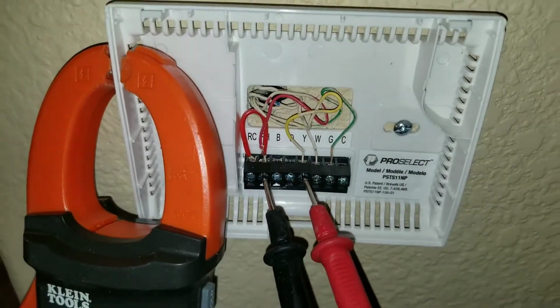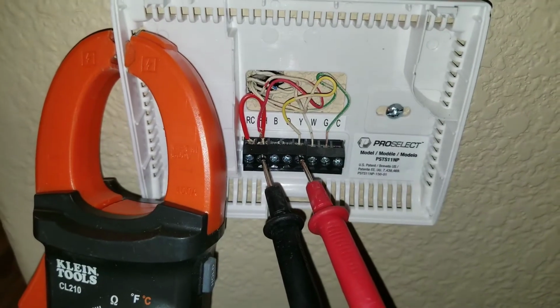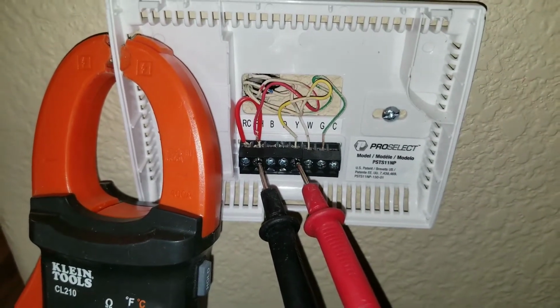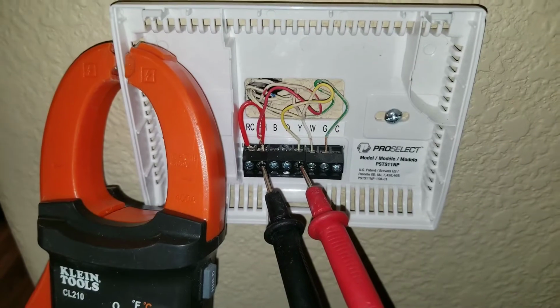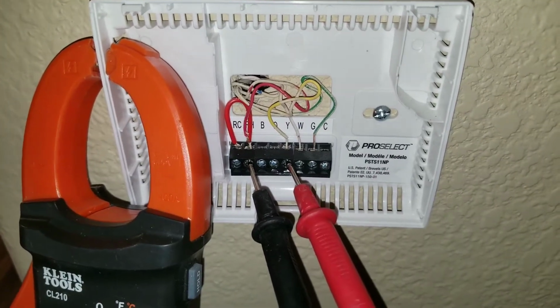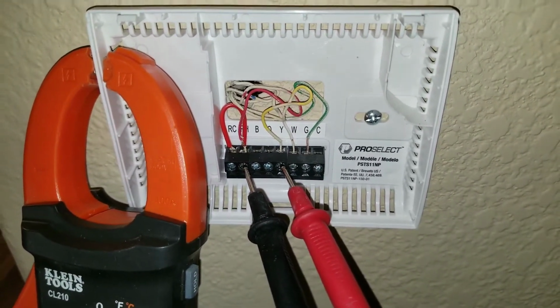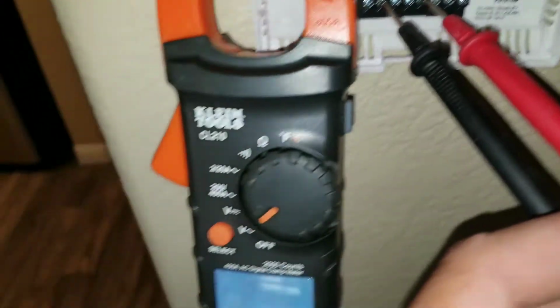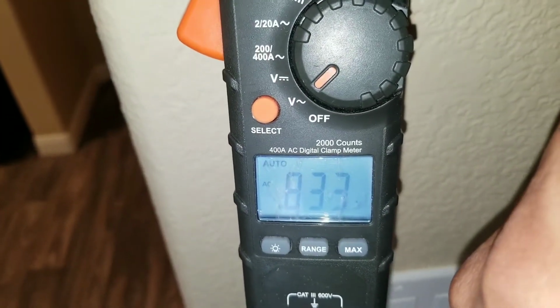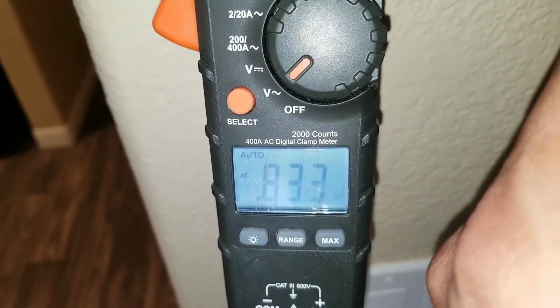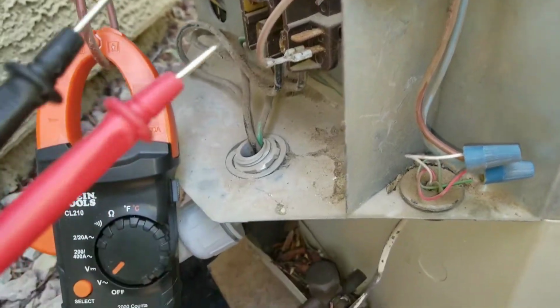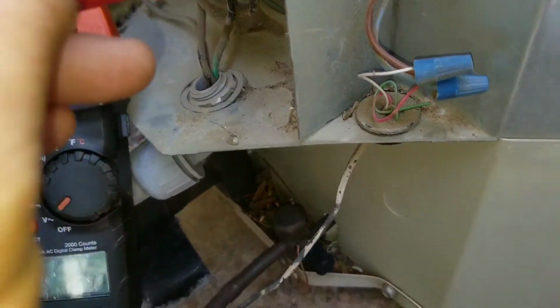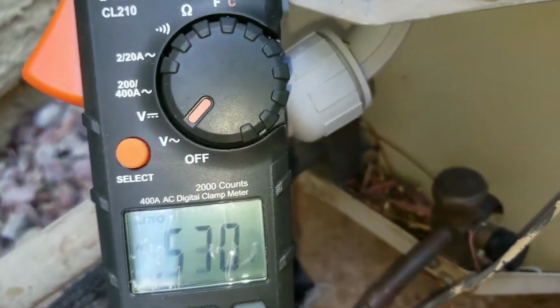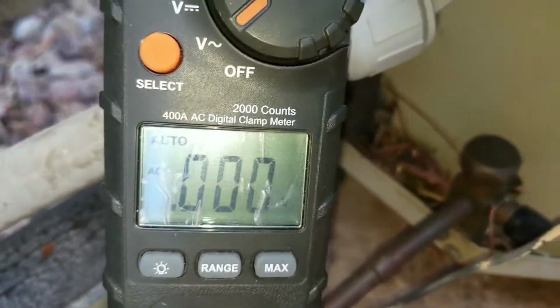So here I have my multimeter and it's on the power coming in, 24 volts on the R terminal. And here I'm on the yellow terminal, which is going to be my condensing unit. And you can see that I do not have voltage coming in. So here I'm going to check my voltage at my contactor. This is my low voltage. And I do not have voltage coming in.